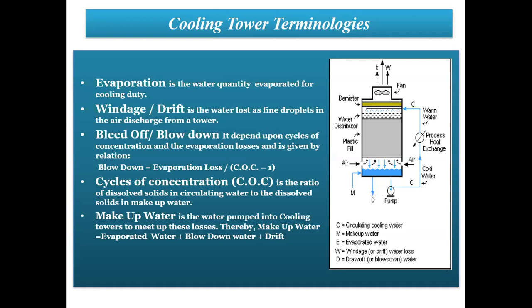Cycles of concentration is basically the ratio of dissolved solids in the cooling circulating water to the dissolved solids in the makeup water. For example, if your makeup water has chlorine of 50 ppm, and the circulating water has a chlorine level of 250 ppm, then 250 divided by 50 equals 5. So you can operate at 5 COCs.